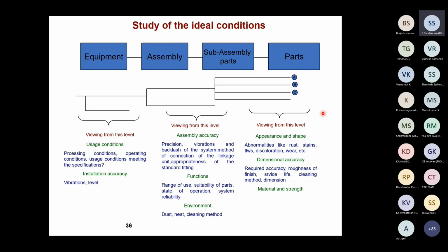There will be some acceptance criteria specifically mentioned in the maintenance manual of particular equipment, but there will be many items where the acceptance criteria is not mentioned. So you need to use your own experience, or discuss with people who have worked with the machines for years, and set the acceptance criteria accordingly. Wherever a measurement has never been done earlier and you don't know the acceptance criteria, at least take the minimum of what it is today. So you need to have a standard mentioned against each point.